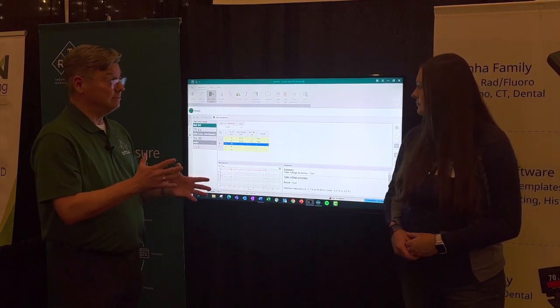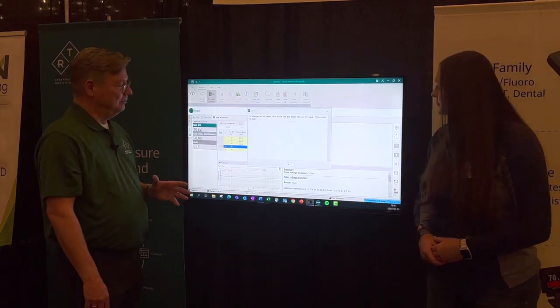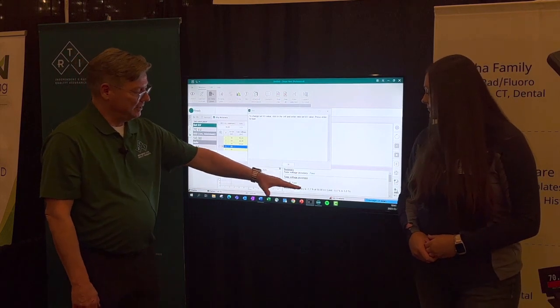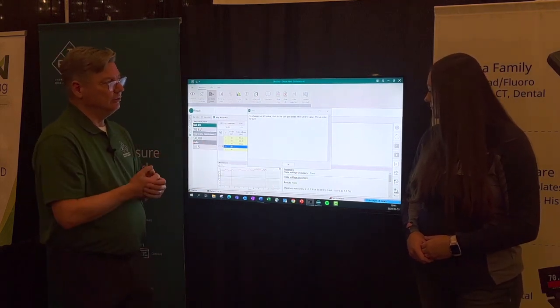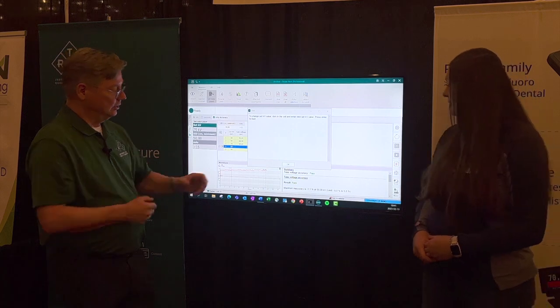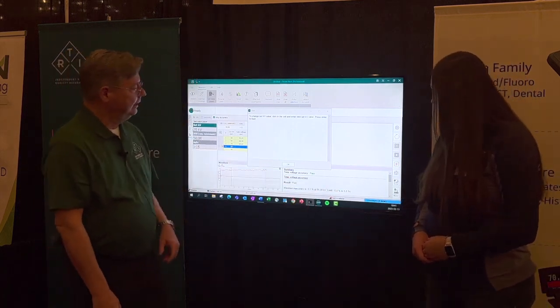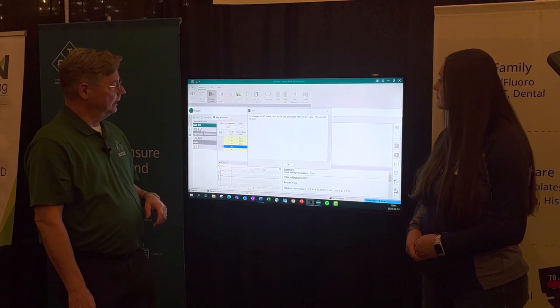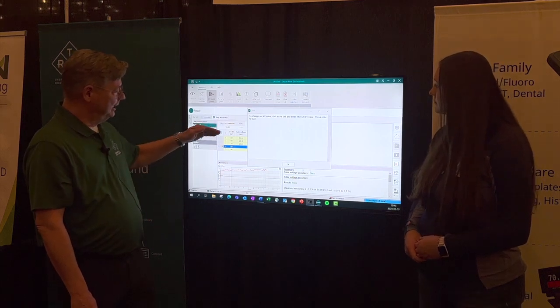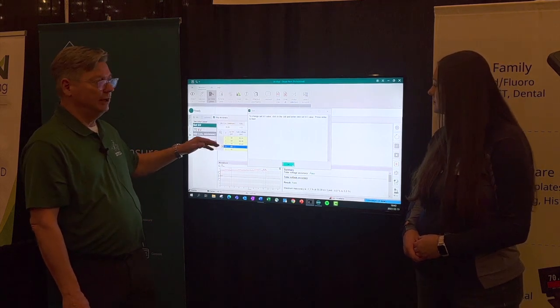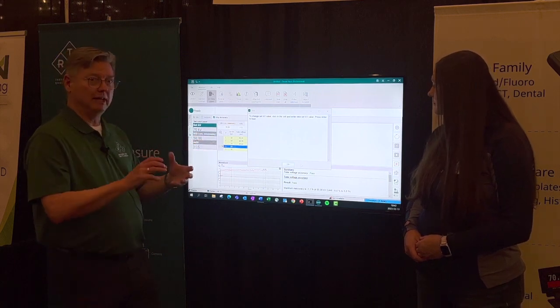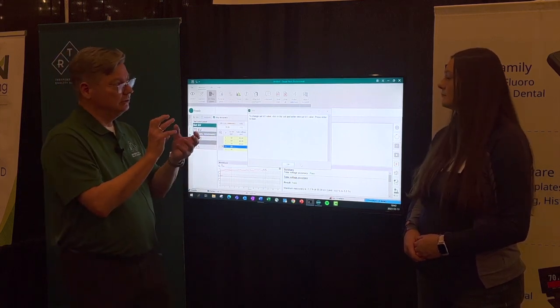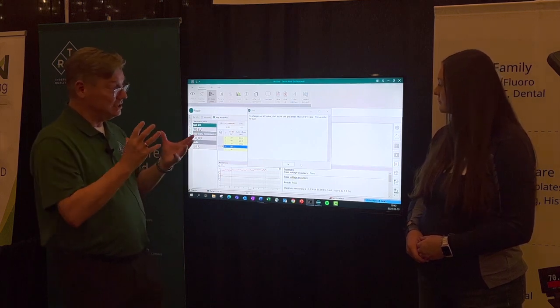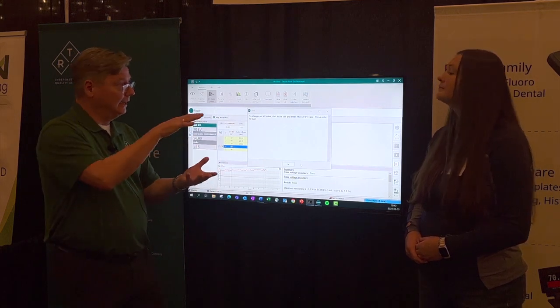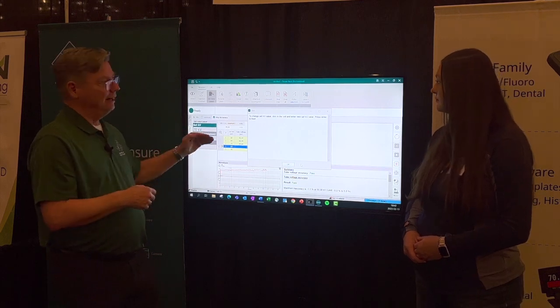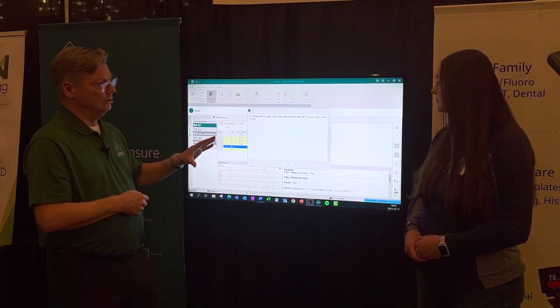The software will calculate the difference in percentage between the set value and the measured value, and determine whether or not it's pass or fail, based on the pass-fail criteria that you've defined when you design the template. So in this case, it's plus minus 5%. Right, and that's the range we're looking at. And along the line, we can also have instructions. So maybe somewhere during the test, you need to add some filters in there. You need to swivel in a copper filter for this specific test, or add a phantom layer, or I don't know what it could be. You can have those reminders pop up as you go along.